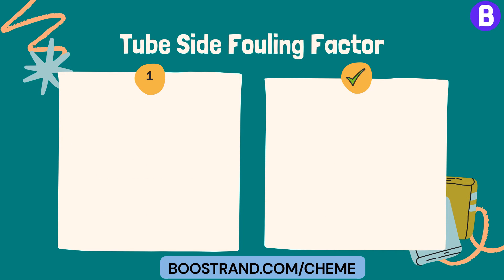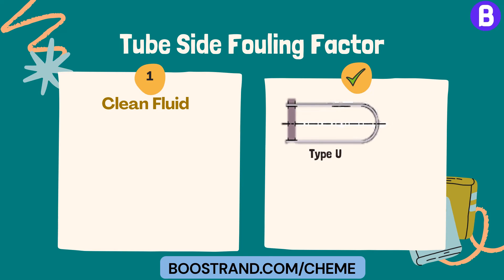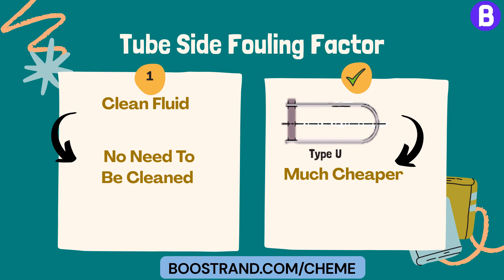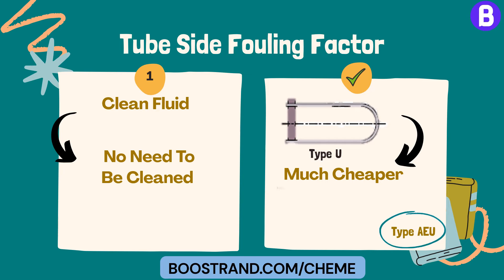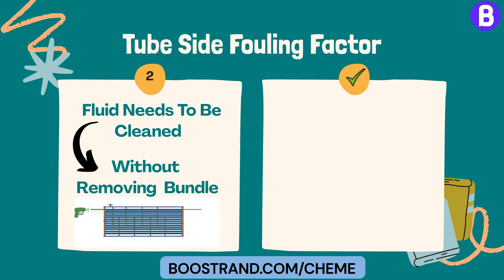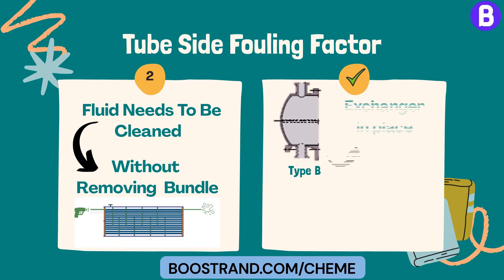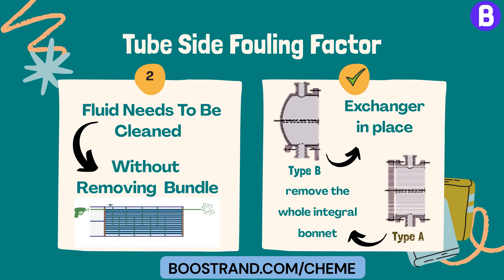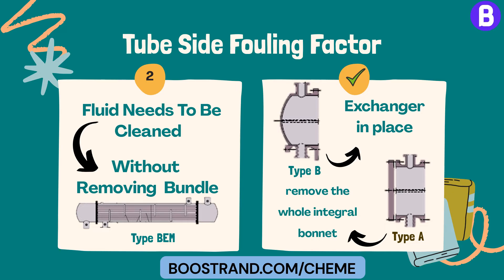If the fluid in the tube side is a clean fluid — a famous example is steam — we can choose a U type for the rear head. It's much cheaper and there is no need to clean it. So depending on the fouling resistance of the shell side, the TEMA type can be AEU or BEU. If the fluid in the tube side needs to be cleaned, this can be done without removing the tube bundle. Even with Type B, we can clean the tube side with the exchanger in place, but we would remove the whole integral bonnet instead of just removing the channel cover as in Type A. Here we can choose a TEMA type of BEL or BEM.